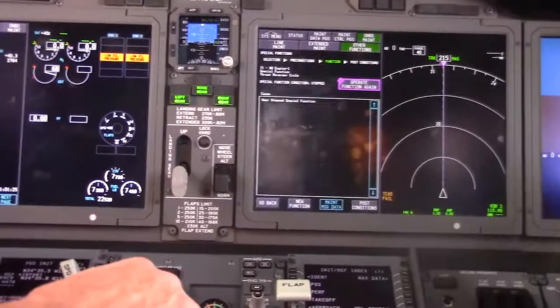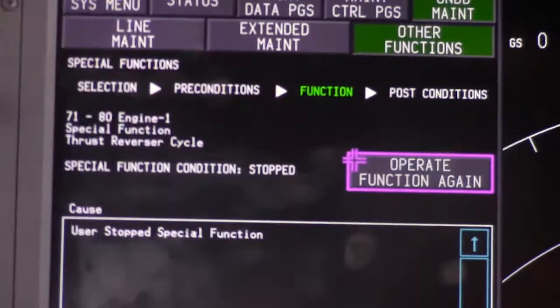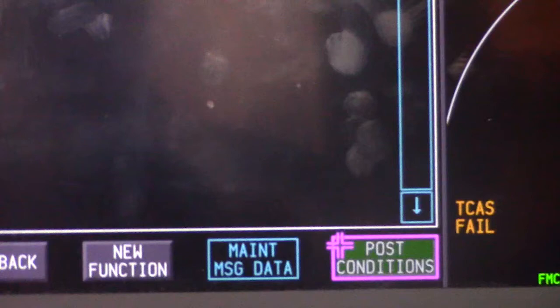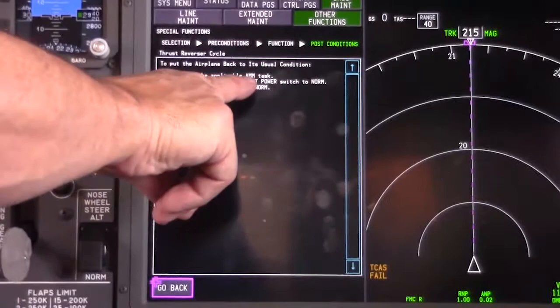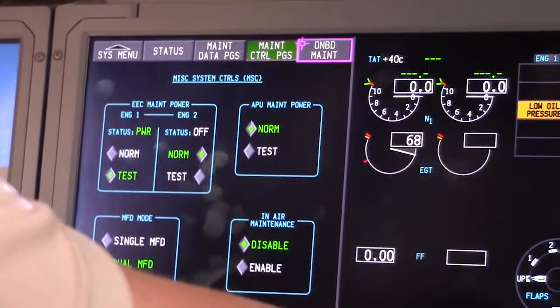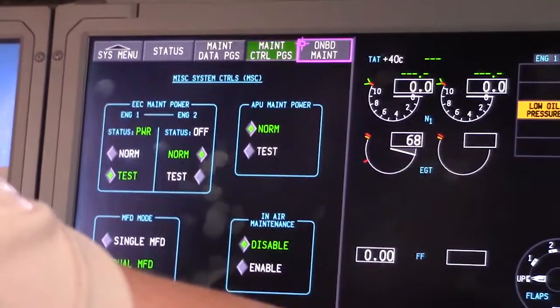We have the option to operate it again if we wanted to, or we can just back out of the screen. One thing to remember is to complete your post conditions, because if you'll remember we powered up our EECs and we need to turn those off. So we want to always complete the post conditions. I'll go down here to post conditions and hit select. It's telling me to switch the EEC power to normal. So I'm going to come back to this screen, maintenance control pages, miscellaneous system controls, and turn my number one EEC back to normal. Now I'm going to set my ground switch back to normal on the panel back here.